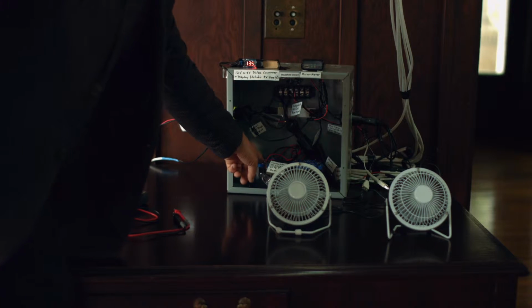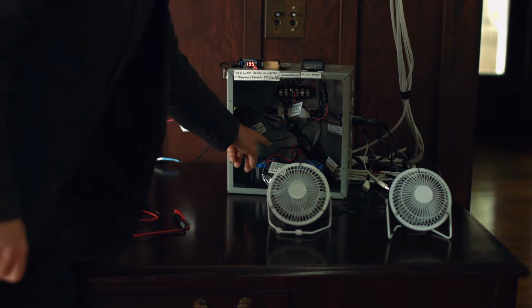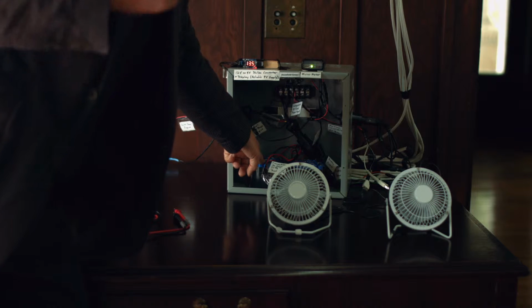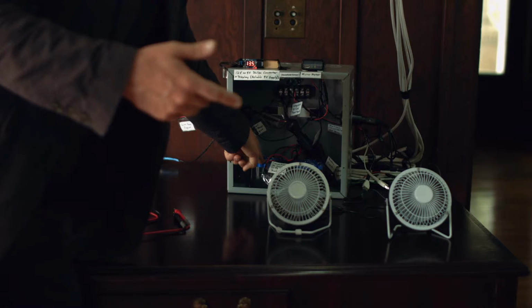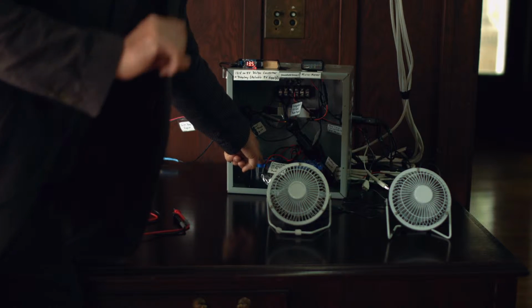Because these batteries are being used every day for the daily demand of the households, rather than using the lead acid batteries, which don't last so long, we're using high quality lithium iron phosphate batteries. The nice thing about the lithium iron phosphate batteries is that they can last more than 2,000 cycles. Because they can last 2,000 cycles, that means we have the possibility of having a system that can last 5 to 10 years rather than developing problems within the first 2 to 3 years.